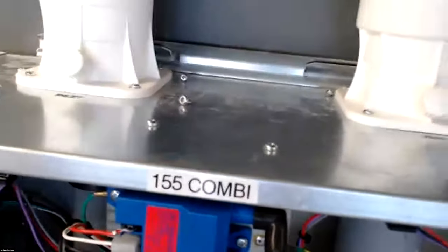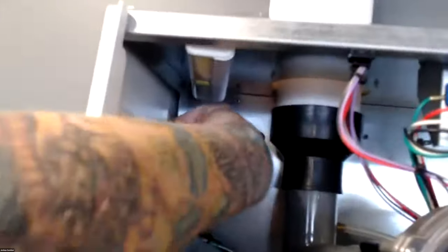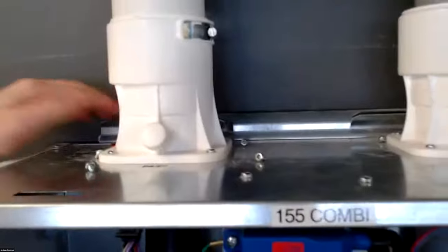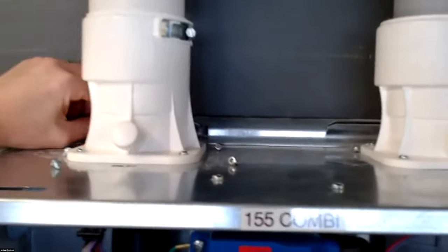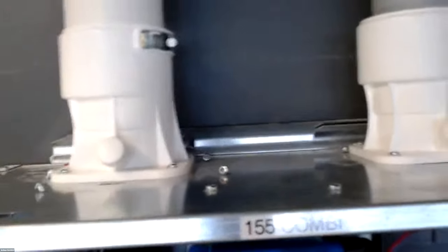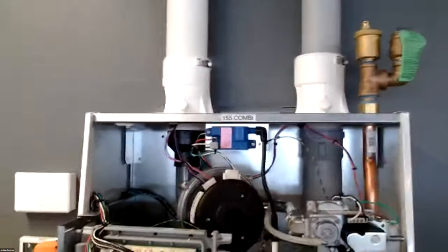One thing with our boilers on the wall hungs, which is really nice, is our bracketing system for hanging the boiler. So if you look, our bracket actually sits above the boiler. In some manufacturers, the hang bracket is behind here on the boiler. With ours, it's actually above it. And you'll be able to basically pick up this boiler, physically look at the bracket and line it up with the pieces of metal that are coming off the top of the boiler and slide it right on. So you don't have to sit there and try to finagle it and hook it up. You can actually physically see what you're doing, which makes it a lot easier to install, which I really like that we did that.